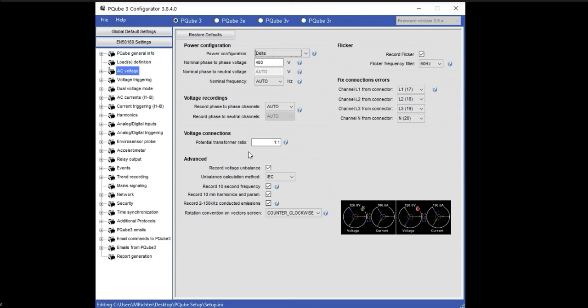However, if I was connecting to a 4160 device, I can't connect that directly to the PQube. I'd want to enter some sort of ratio for the potential transformers being used. A common ratio for 4160 is 4200 to 120 volts. The applied voltage to each PQube channel will be 120 volts, but the real voltage inside the PT is 4000.